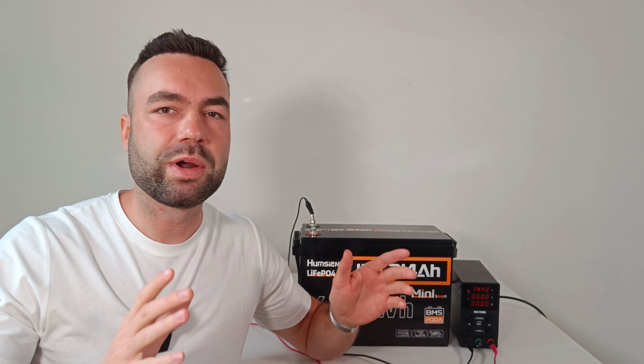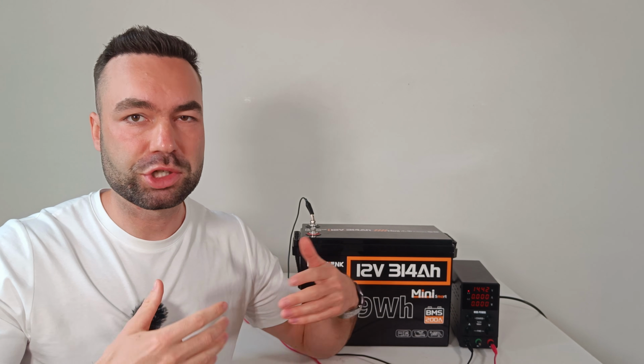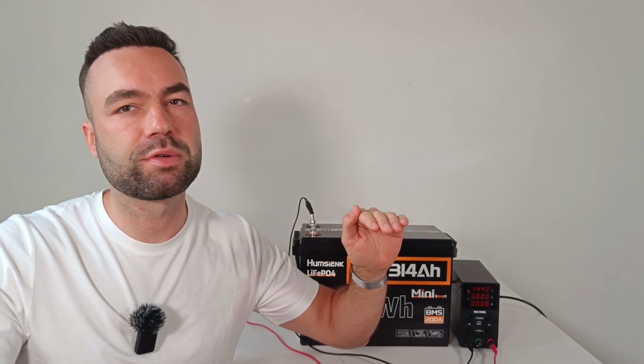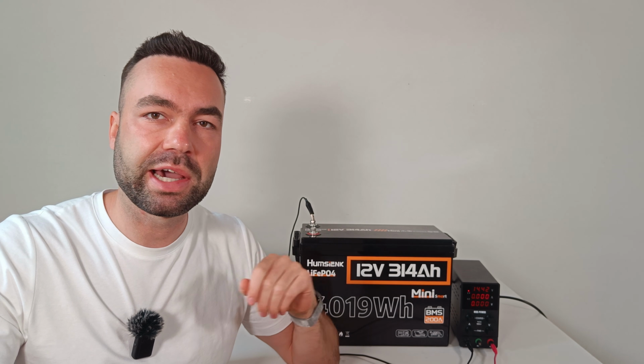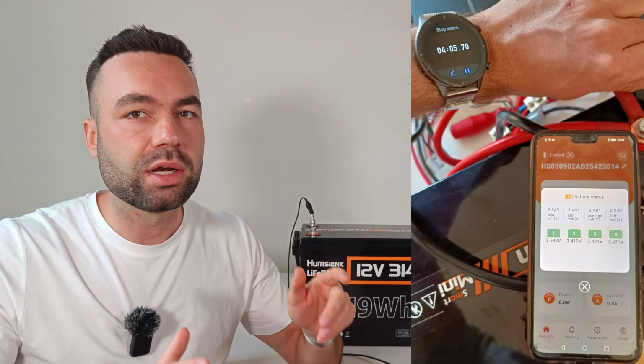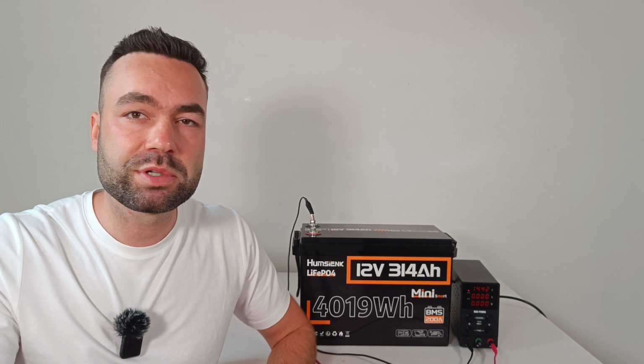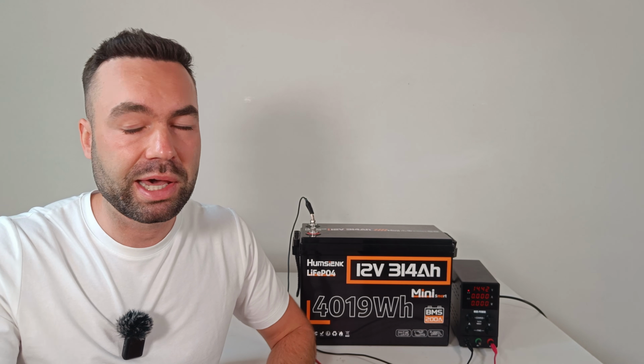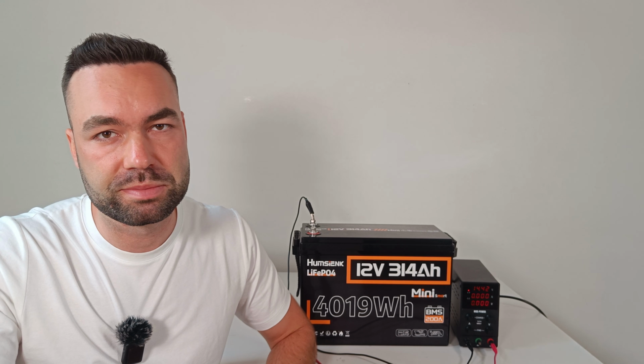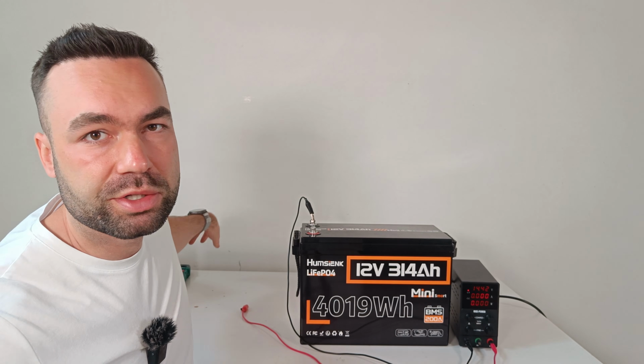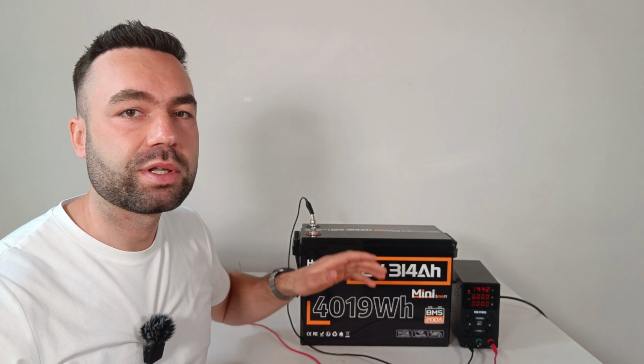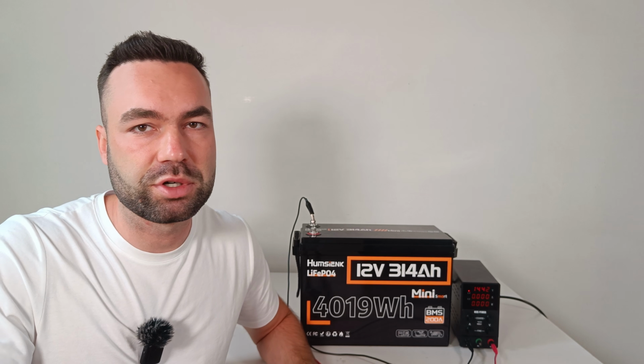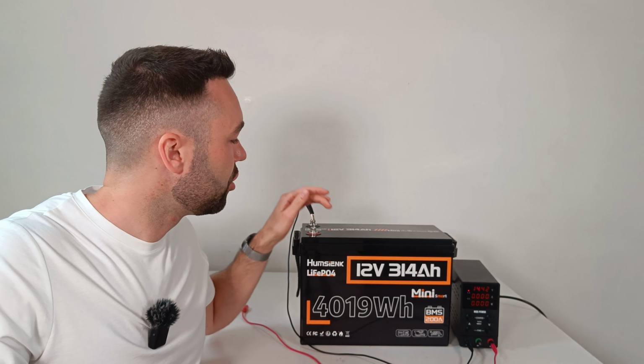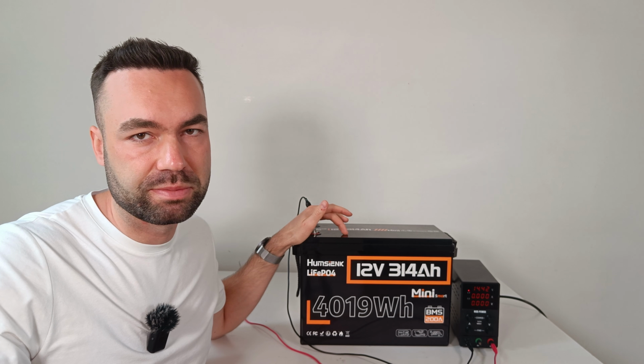The only time balancing can happen is during the charge phase, between 3.45 volts and 3.65 volts. With a 20 amp charger, that window lasts about 5 minutes. You can let it charge at 1 amp, but that would take a long time and is not a practical solution. I checked the 100 amp hour version and that one does balance without an active charge, so the issue appears to be specific to this battery.